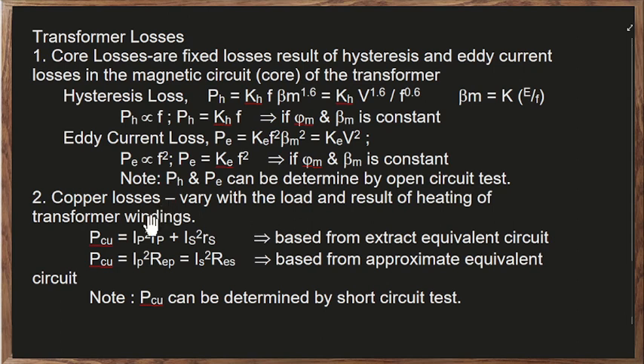Then the copper loss. The copper loss will vary depending on the load and is the result of heating in the transformer winding. So it will depend on what load we put on our transformer. We could have that in terms of the primary and the secondary. So we have I_P squared R_P plus I_S squared R_S.